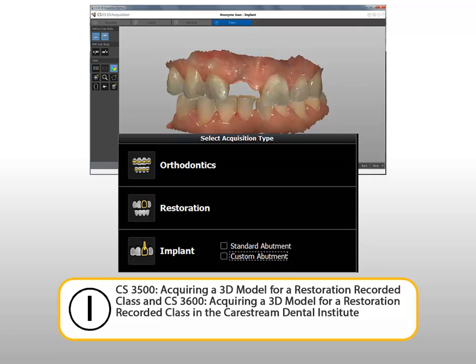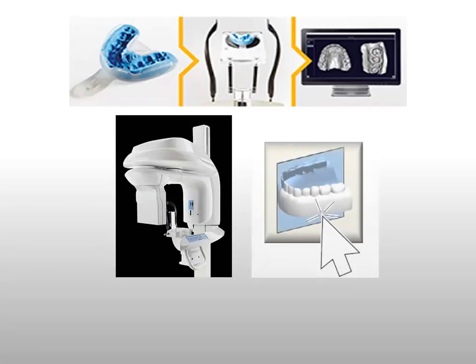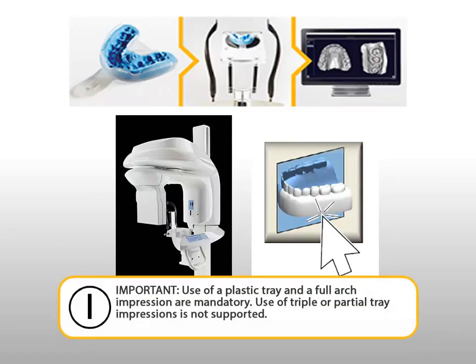You can also acquire a 3D model from a conventional impression — silicon or alginate — obtained using a CareStream Dental CBCT unit and the 3D object acquisition module. Use of a plastic tray and a full arch impression are mandatory. Use of triple or partial tray impressions is not supported.